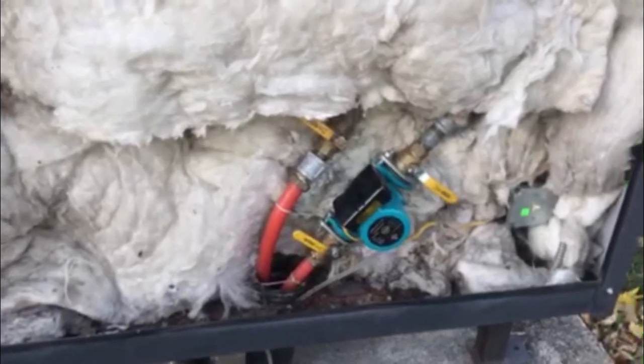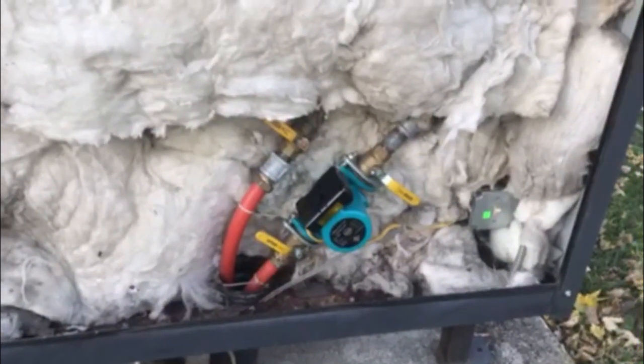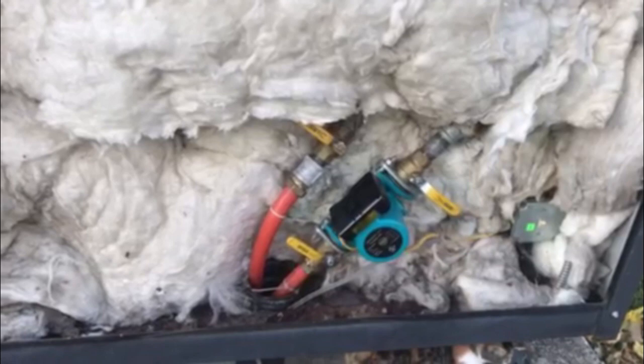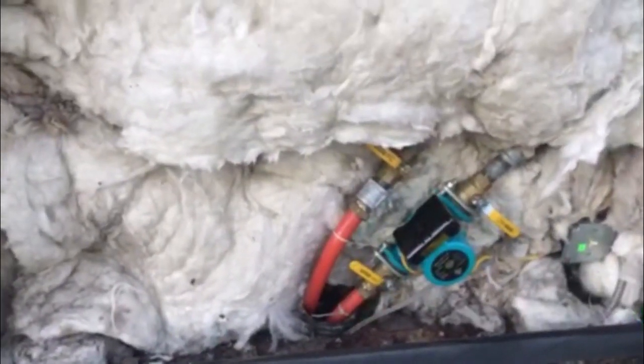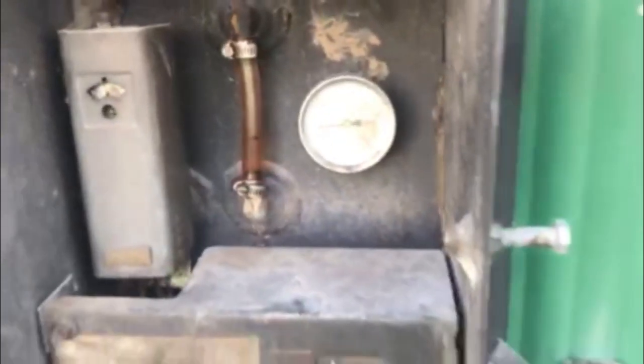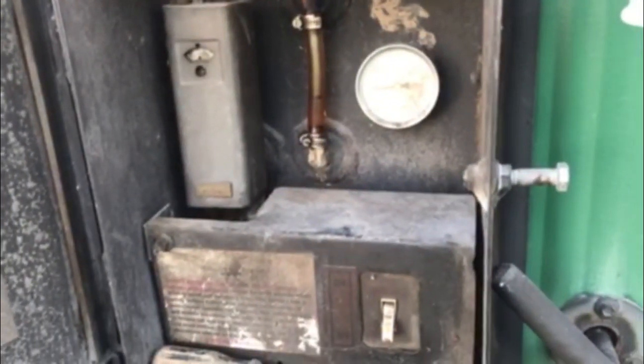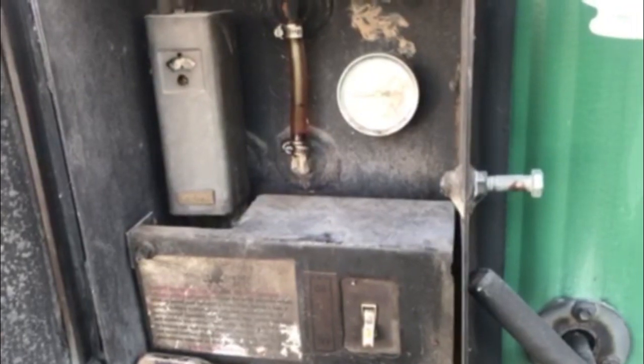I came around to the back and turned the pump off and the valves off, just to try to isolate the boiler from the lines and from the heat exchanger in the house. I put a mark on the tube, and even though you can't really see it, the water level is staying put right there at the mark. So the boiler is okay, and now I've got to figure out where the leak is.